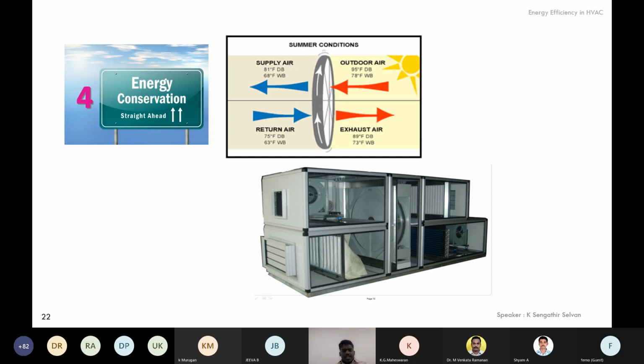As we discussed earlier, we need fresh air mandatorily, because we need to dilute the CO2 concentration within the office space for human health and better productivity. Now here, bringing in fresh air is going to increase the energy consumption. There is no way around it. So we have to see how we can conserve the energy used to bring in the fresh air.